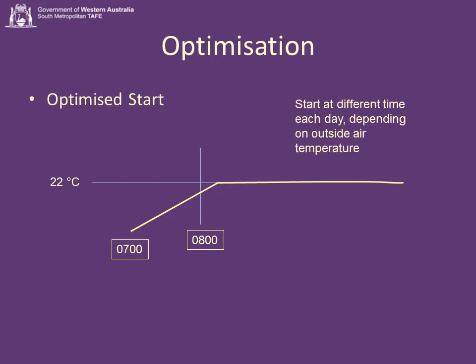This is what we can do with a networked control system. We monitor the outside air temperature and the building temperature, and instead of starting at 6 o'clock, we start it at precisely the right time so it's nearly perfect at 8 o'clock when people arrive. Honestly, they won't take their coats off until about 8:30 anyway, so it doesn't need to be perfect at 8. This will save a good hour's air conditioning every day.